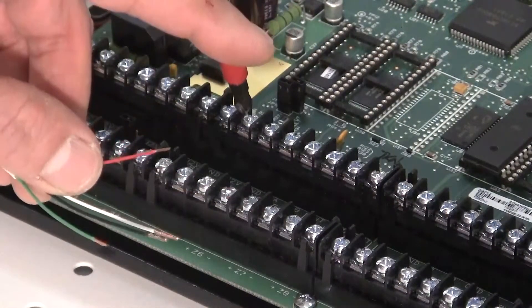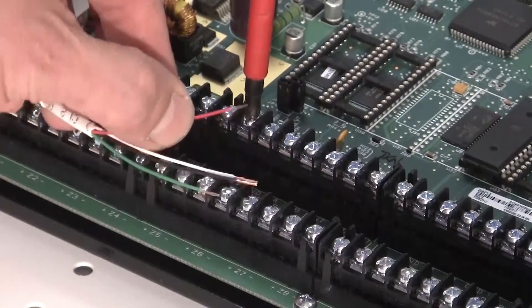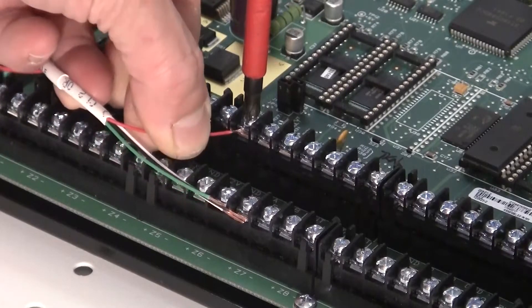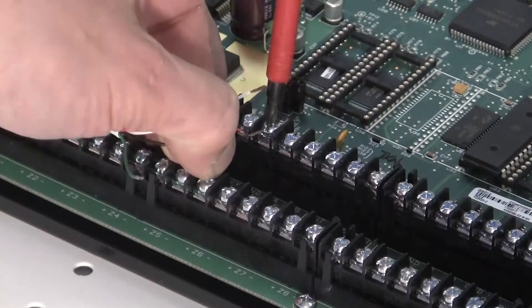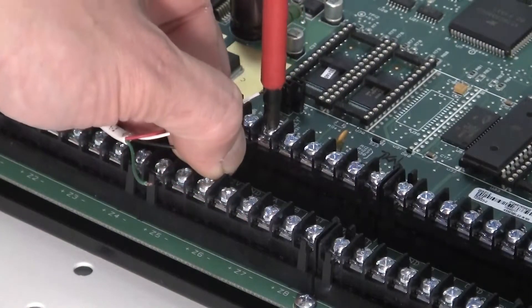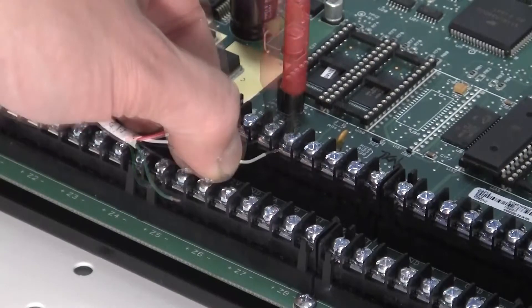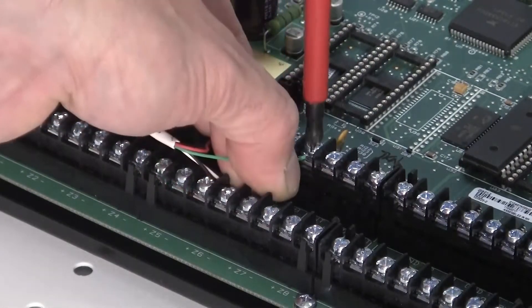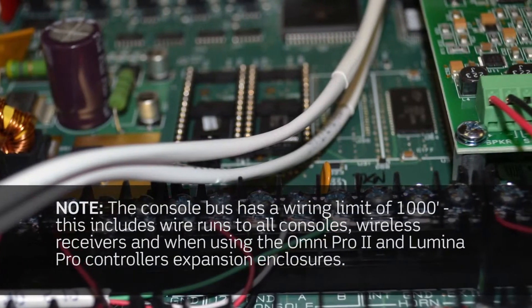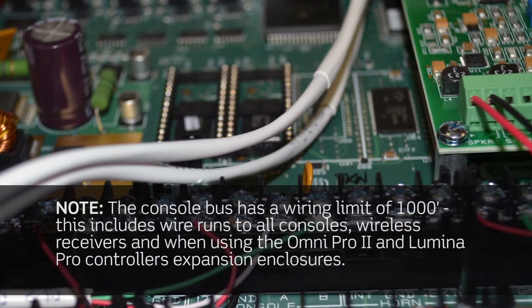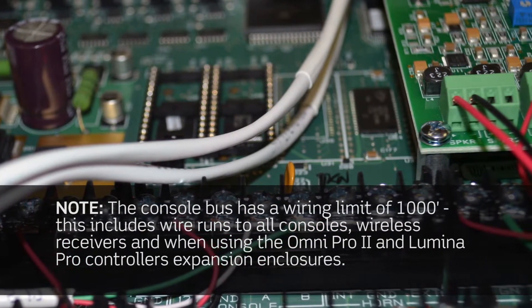Using 22-gauge 4-conductor wire, connect to the terminals as follows: Red to 12V+, black to ground, yellow to A, green to B. Connect additional consoles if used to the same terminals in a similar manner.